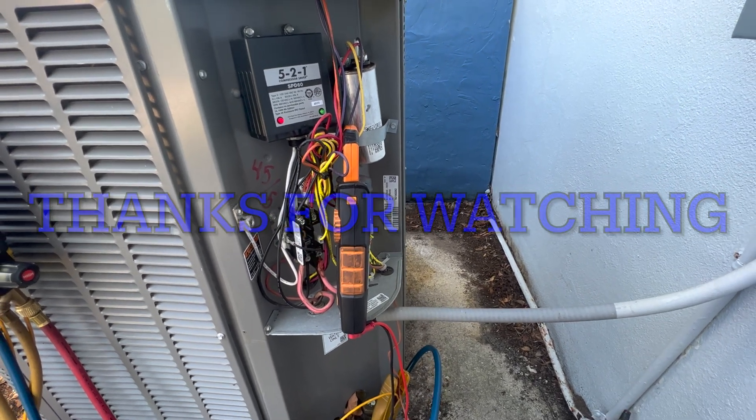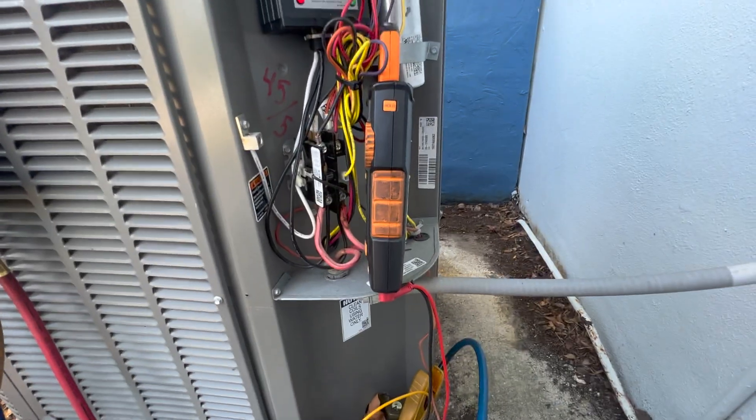This cap is rated for 45 and 5, so it's right on point. I probably wouldn't recommend to change it — I usually change it if it's plus or minus ten percent of the rated value.